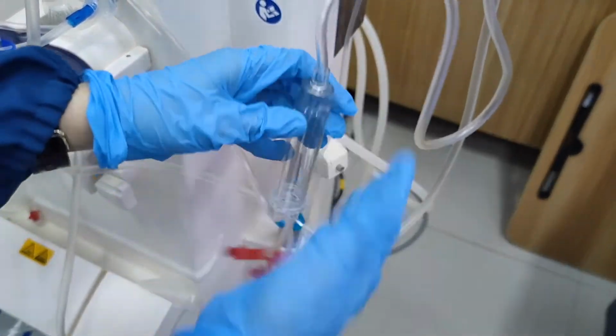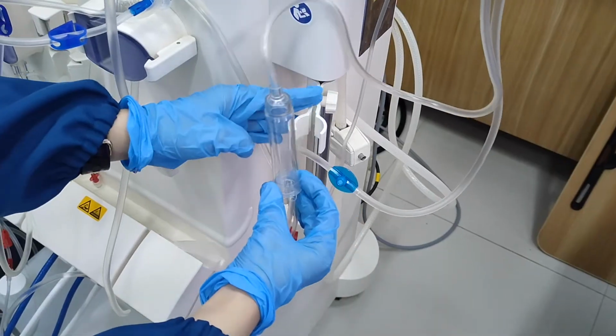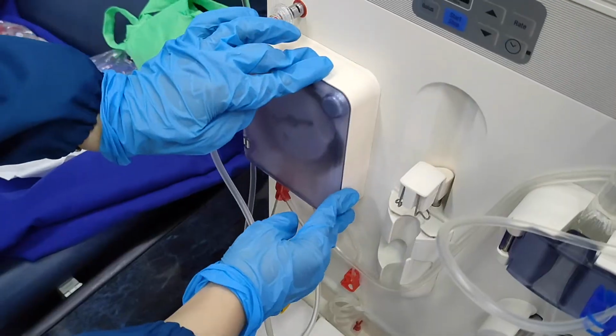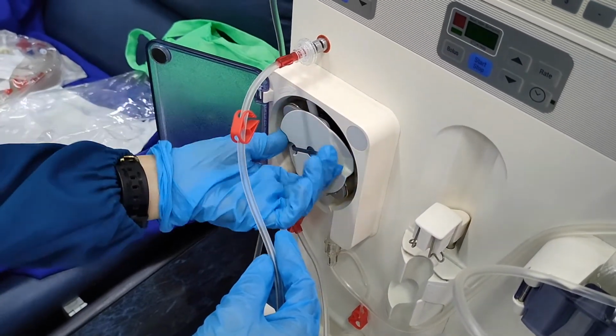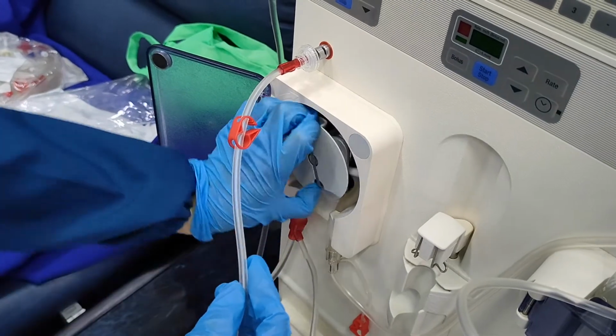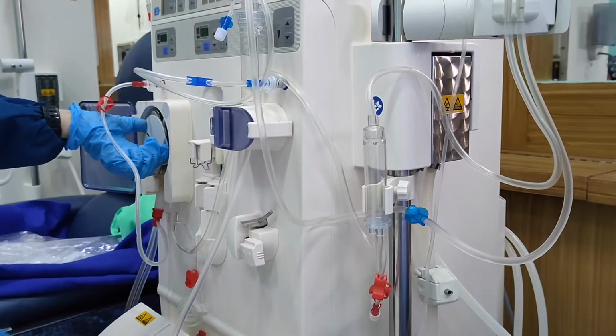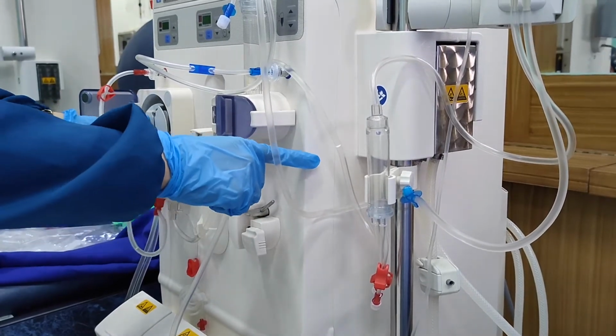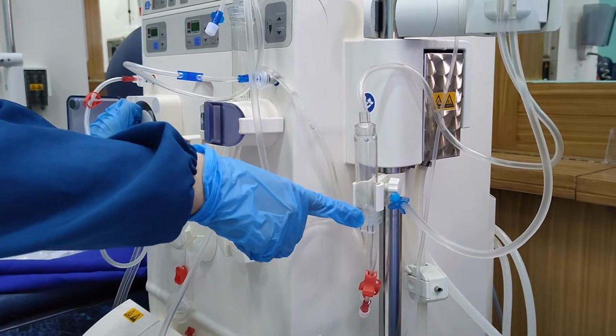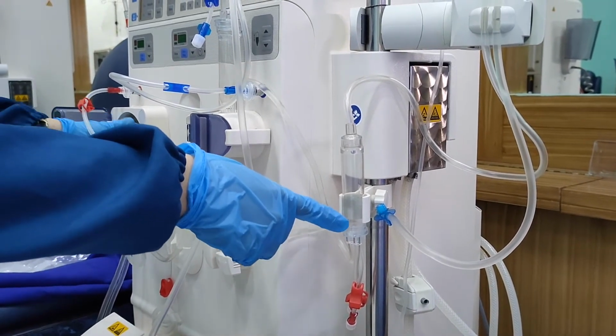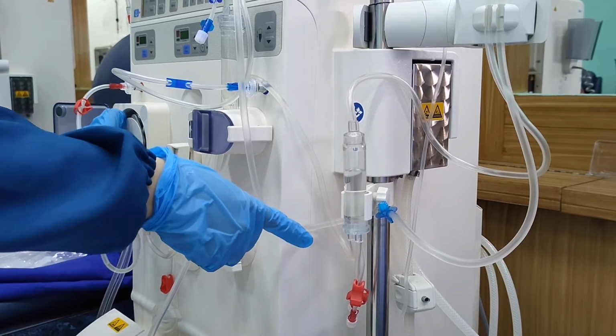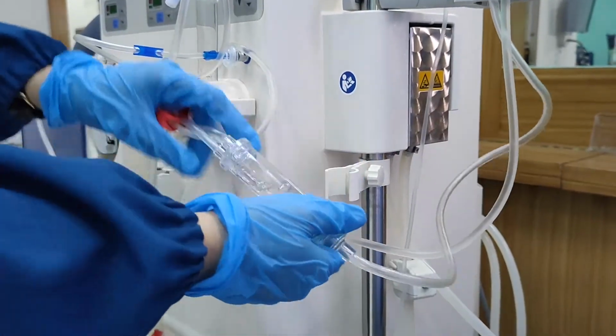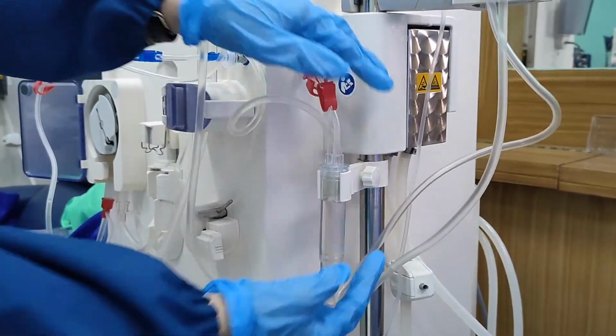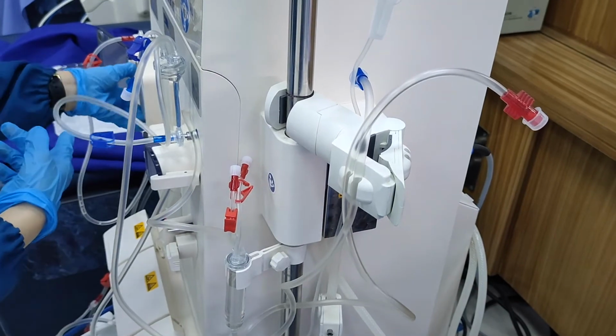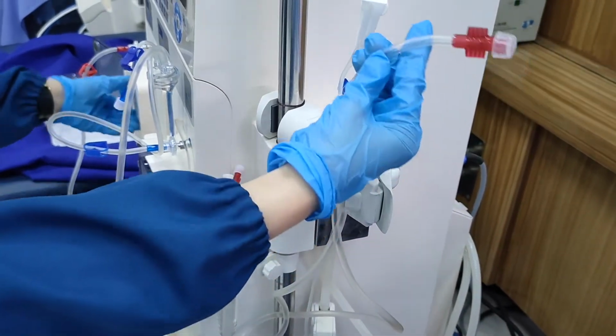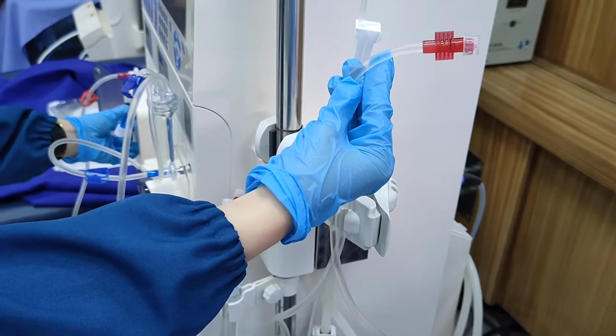Next, invert the arterial chamber. Then, manually turn the blood pump until the arterial chamber is 3/4 full. After the arterial chamber is 3/4 full, place the arterial chamber upright. Then, continue to manually turn the blood pump until the dialyzer port is filled with NSS.